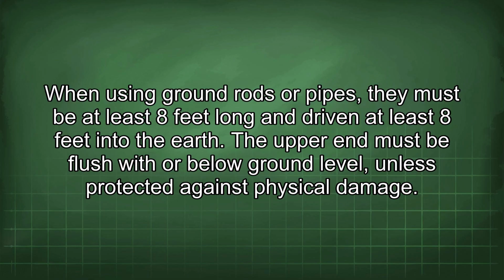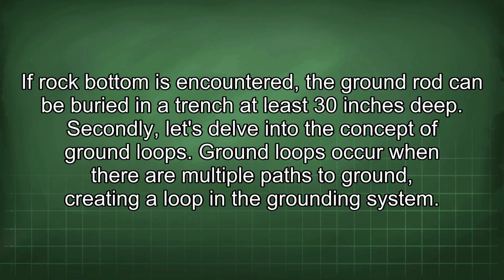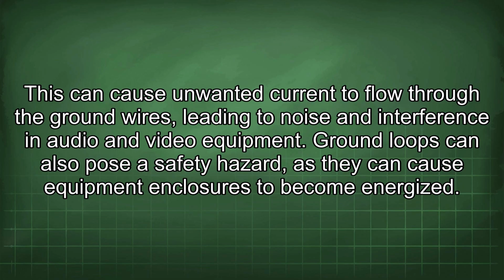The upper end must be flush with or below ground level unless protected against physical damage. If rock bottom is encountered, the ground rod can be buried in a trench at least 30 inches deep. Secondly, let's delve into the concept of ground loops. Ground loops occur when there are multiple paths to ground, creating a loop in the grounding system.